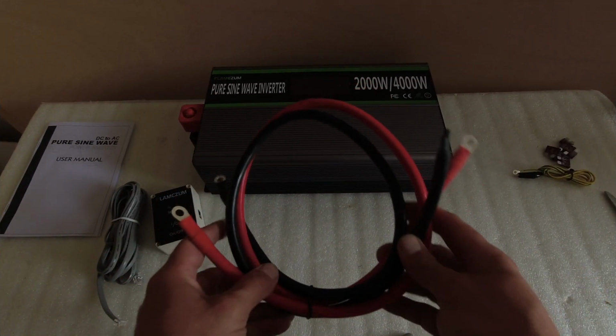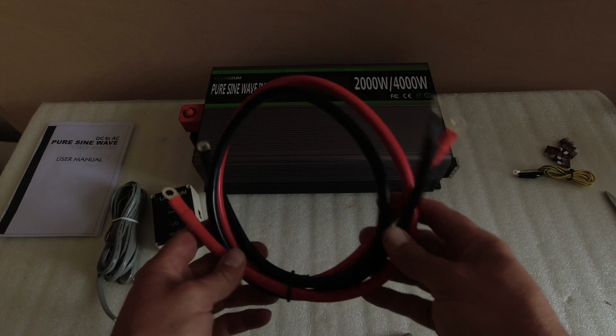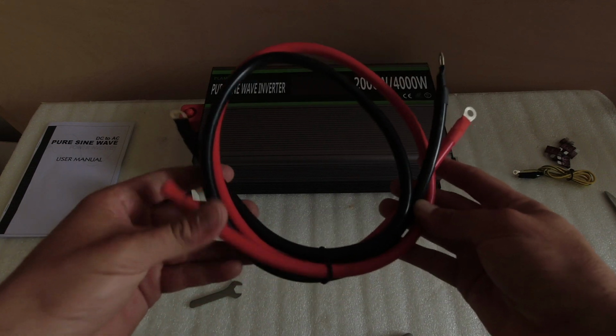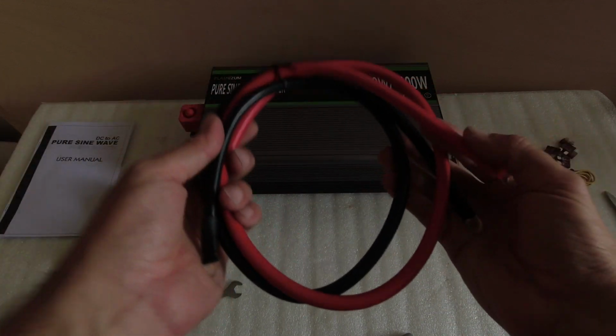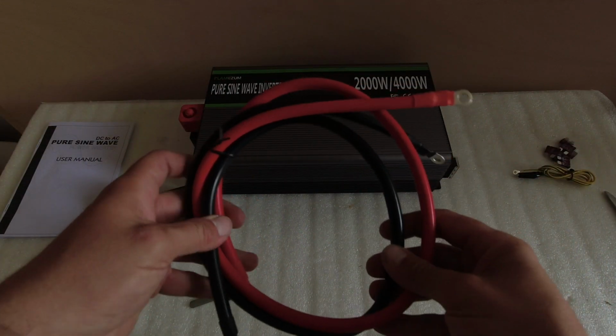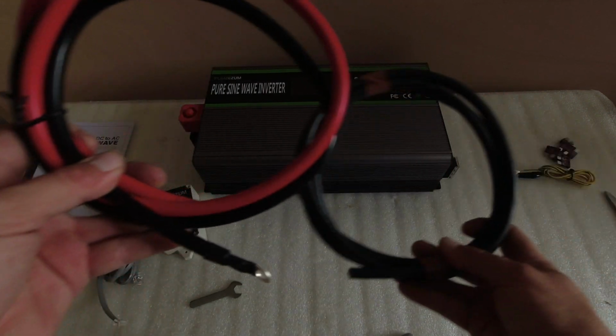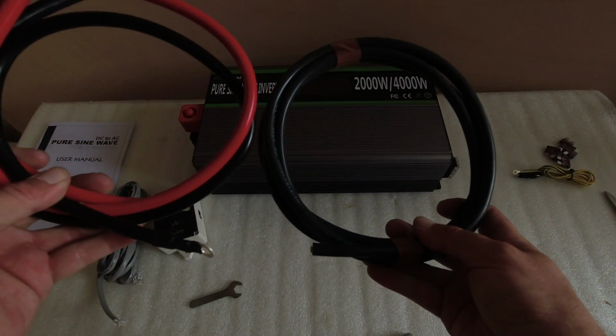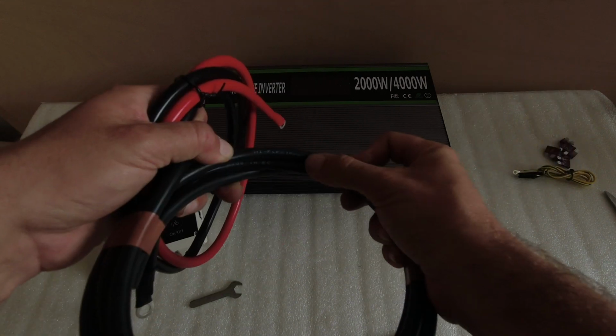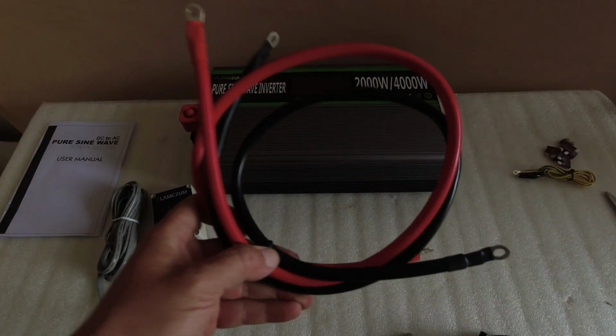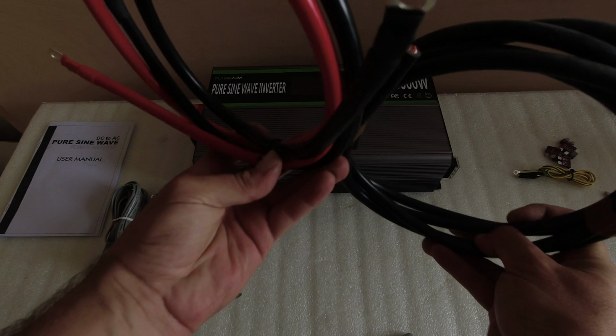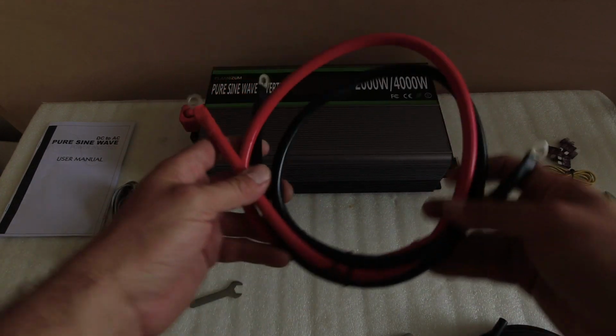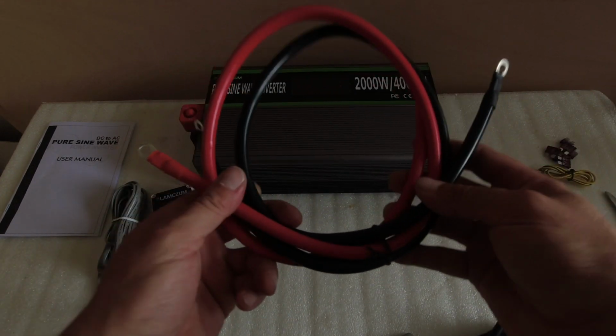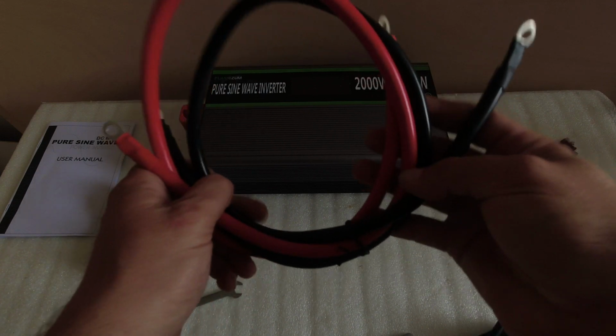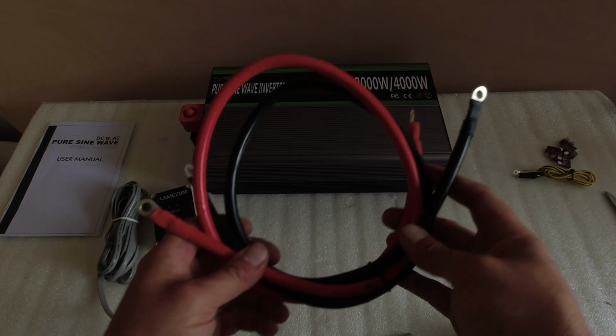The battery cables supplied with the inverter don't have any writing on them, so I don't know exactly how thick they are, but for comparison I have here a 16 square millimeter cable, which looks about the same, so I will presume this is 16 square millimeters, which can carry 110 amps.